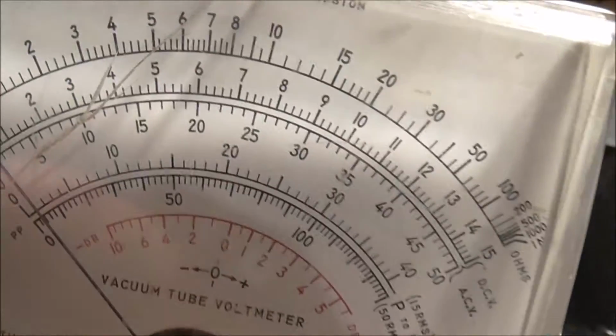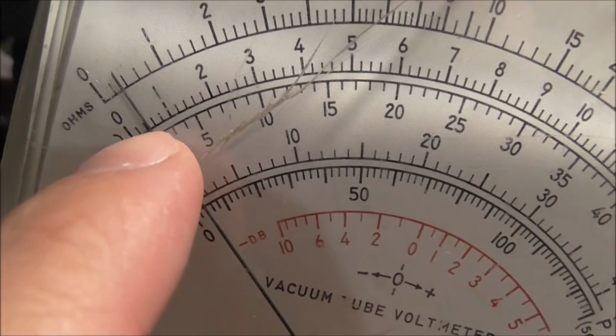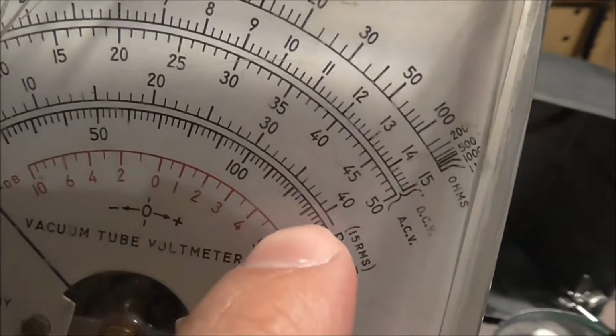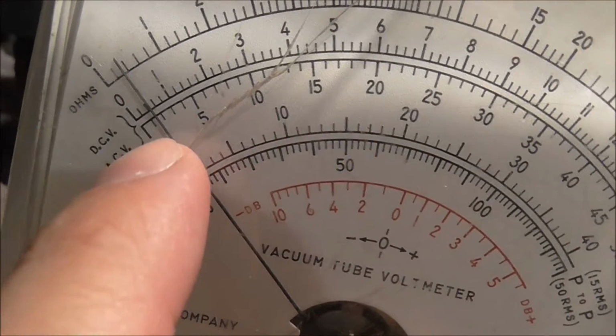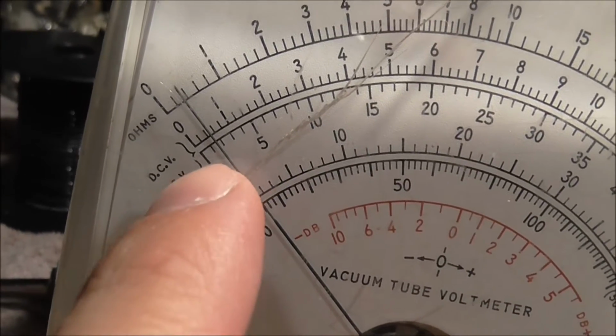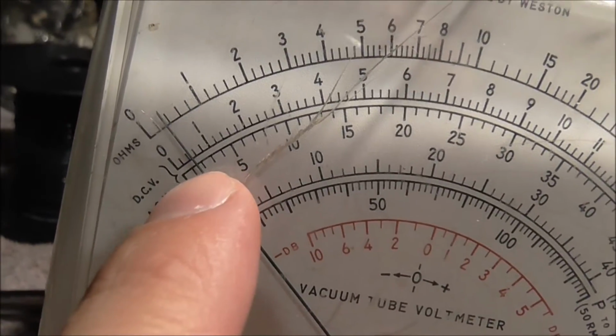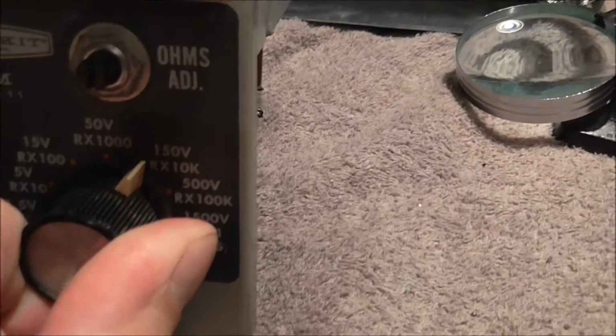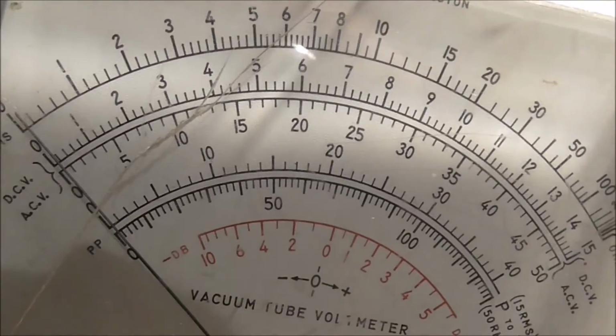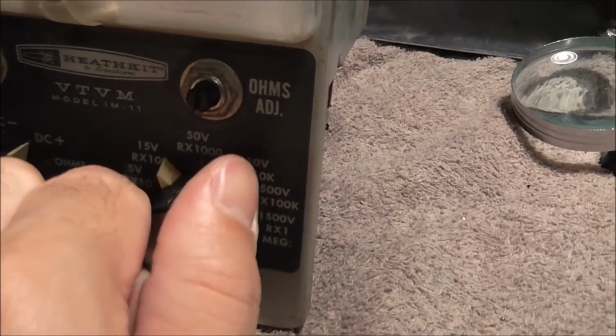The 50 volt scale, it's actually reading about 50. It's reading actually not too bad. That's 5, so that'd be about 1.5 there. And then any higher than this, we're definitely not going to see anything. Yeah, the meter's basically at 0. So we know that the ranges are working correctly here.